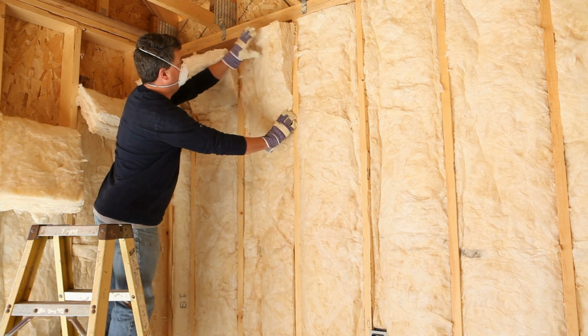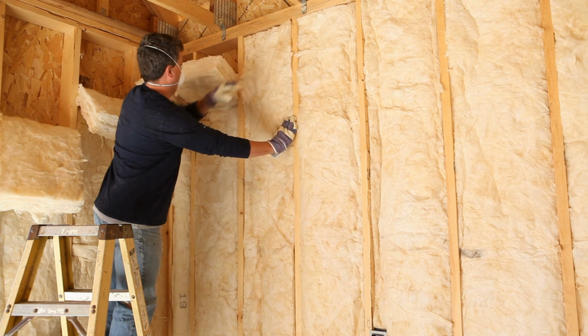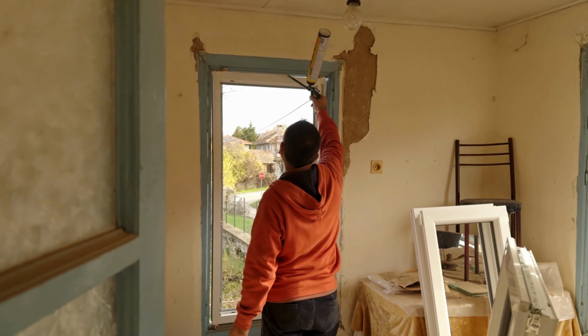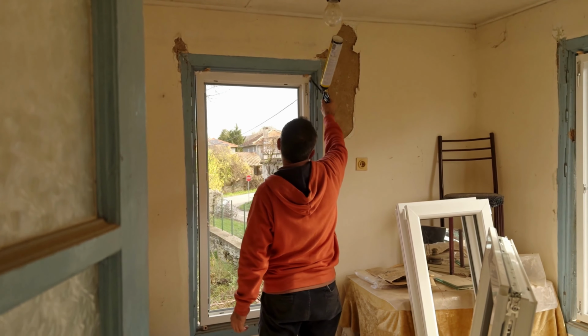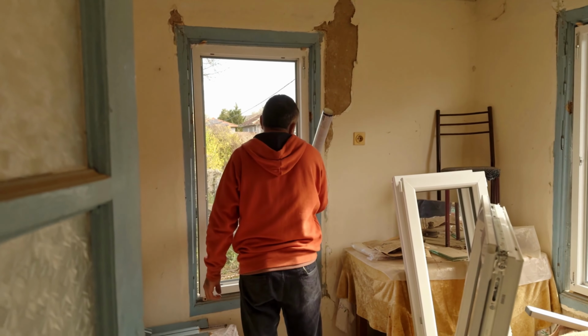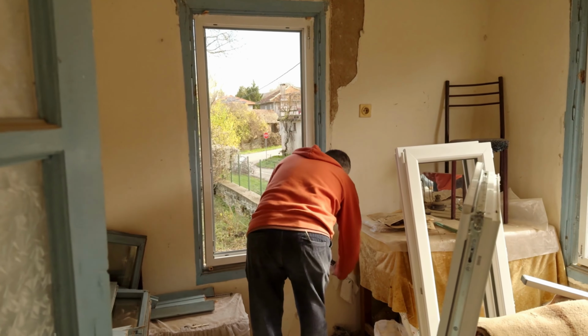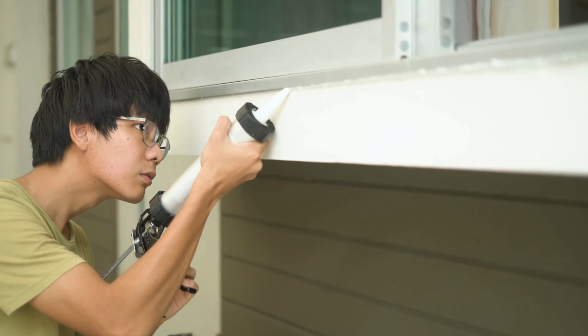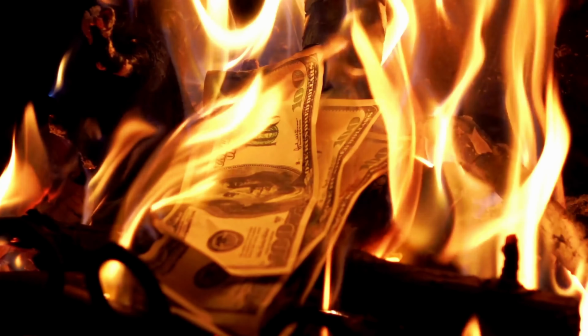Air sealing is probably the most overlooked thing, and it's one of the highest returns you could get when done correctly. Perfect insulation doesn't matter if your conditioned air is sneaking out through gaps, penetrations, and bad transitions. There's something called a blower door test that finds every single one of those leaks, and then you can seal them up cheap. It's not expensive to seal them up, but if you ignore them, it is expensive. Get that blower door test, seal up any leaks, and you'll see savings in the long run. Sealing them up is cheap; ignoring them is expensive. Look into that.